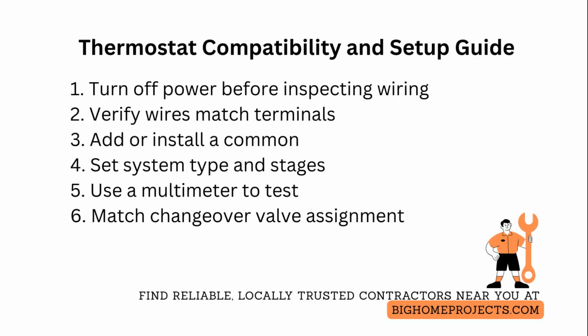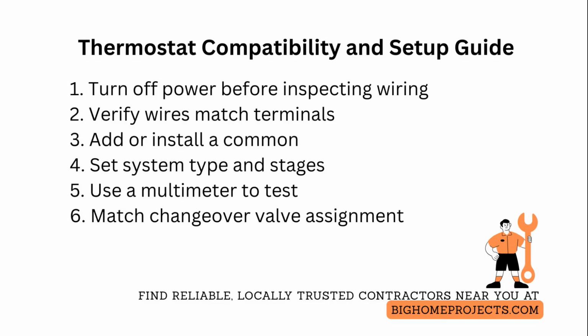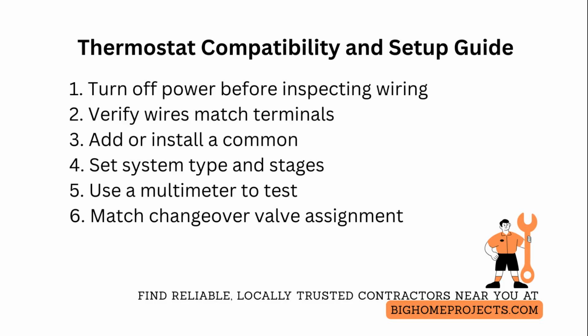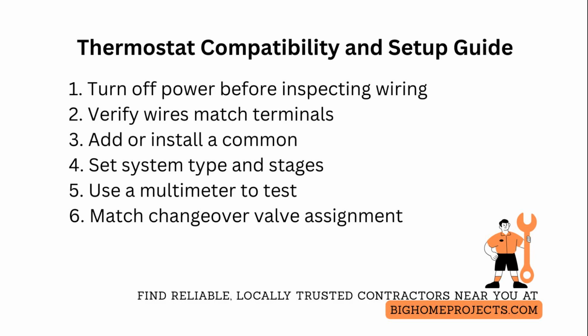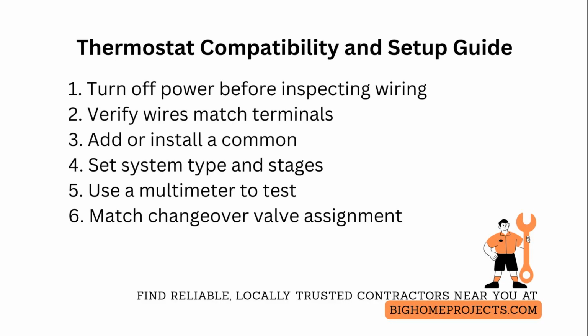Select gas, oil, electric, or heat pump and specify single-stage or multi-stage operation exactly as the equipment requires. Misset jumpers commonly disable compressor control or auxiliary heat. Use a multimeter to confirm the thermostat is receiving 24 volts and that the call for heat or cool closes the correct circuit at the stat and at the air handler. This isolates wiring versus control board problems.